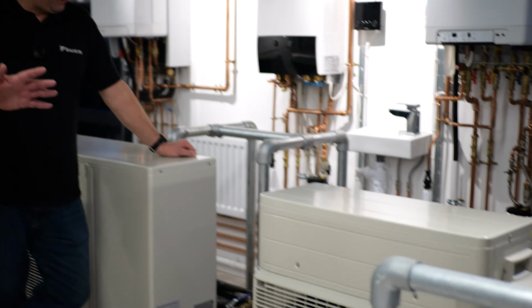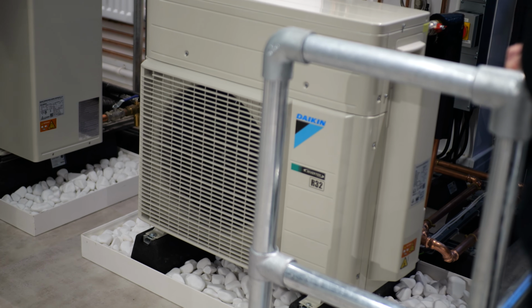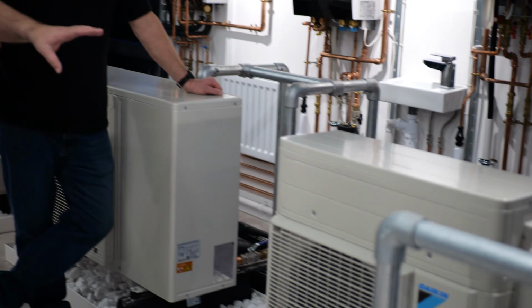You're probably looking at an equilibrium point somewhere between 3 and 5 degrees. The heat pump will heat your property down to around 3 degrees ambient minimum generally, and then the boiler will kick in to heat the property.